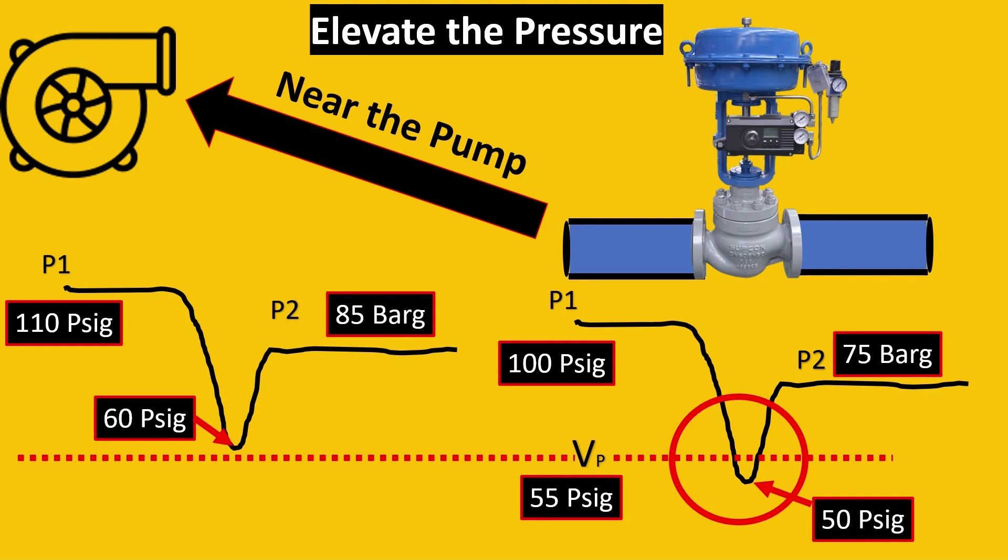The amazing thing is, look at the vapor pressure curve - it was 55 psig. So it is going above, and we have already saved cavitation without adding anything, just moving the control valve which we have to install anyway. Isn't it amazing? If you compare both areas, you would see that even though the pressure drop is the same, cavitation is not happening in the second case while it's happening in the first case.